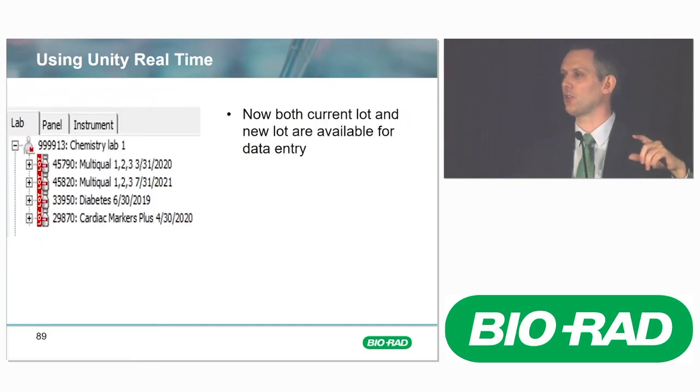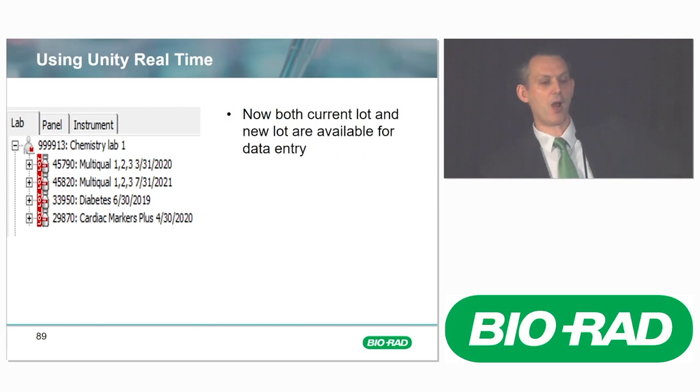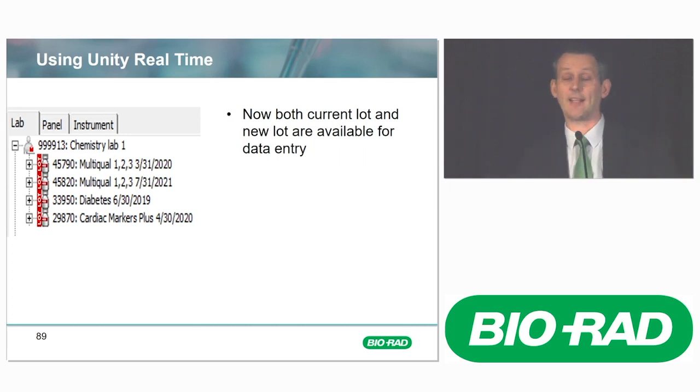So when you duplicate your lots, you'll see that in our navigation, we now have the 2 lots next to each other. And that is nice because on some instruments, you can run your lot already as a new lot number, and they can both be automatically transmitted to your software, and the software can capture the QC and calculate everything for you. I know not all systems can do that, and sometimes your middleware or your LIS might not be able to handle 2 lots at the same time. So then I know some labs just run it as a patient, their new lot, and then would have to write down or manually go enter those results into the software. So that can work too. But some instruments already have the power of exporting both lots at the same time, and you just capture both.